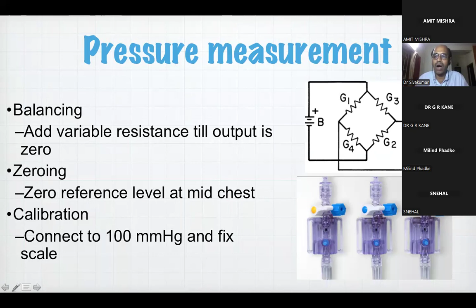Balancing is telling the technician to zero the transducer, and he presses the button 0, and immediately what the machine does is it adds a variable resistance and maintains the output at a particular amount of current that gives a 0 value on the pressure tracer.